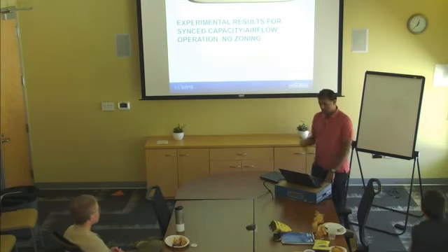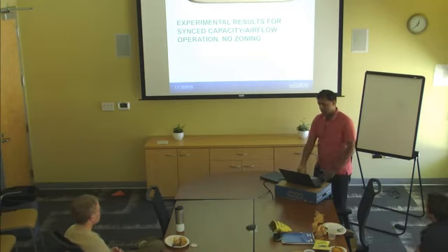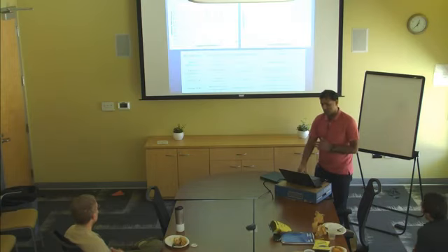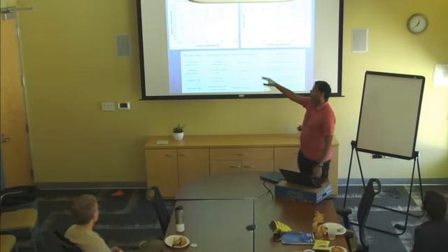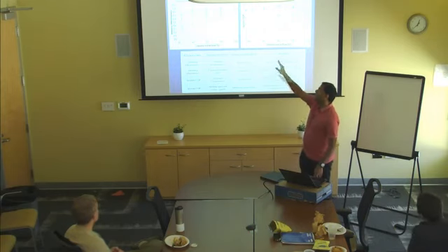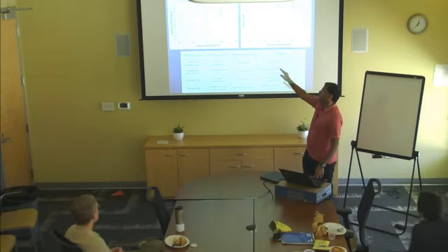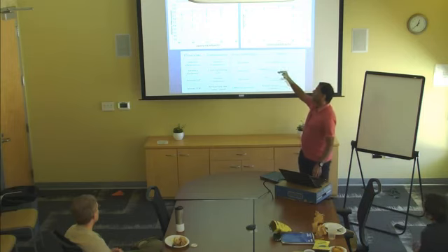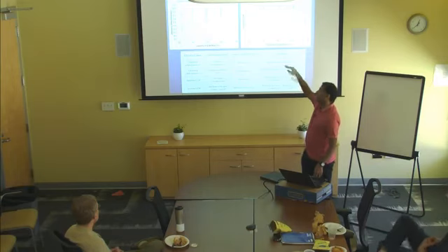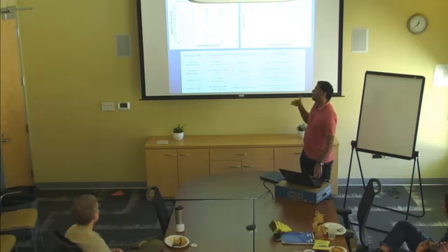So I'll show results for each type of test I did. First is when the capacity and airflow rate were synced and there was no zoning. So the graph on the left side is delivery effectiveness versus capacity and airflow at 4 different outdoor temperatures, or duct zone temperatures. So you can see that as the duct zone temperature increases from the green line to the blue line, the delivery effectiveness drops sharply, and that's understandable because the heat gain in the ducts increases.